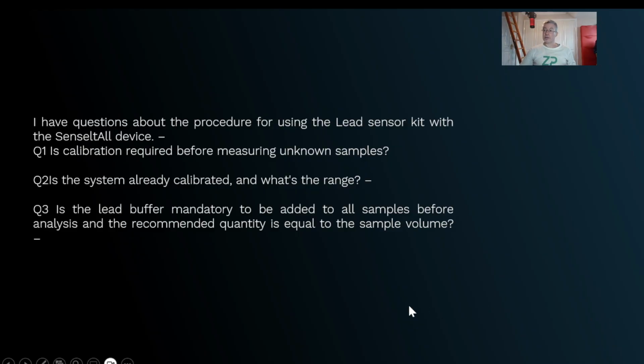Right, so now let me just do a quick recap. Is calibration required before measuring the unknown sample? No, you just saw me. What I've done is I've taken one volume of the unknown plus one volume of the buffer, so that allowed me to control the pH and the ionic strength of that sample. I didn't do a calibration because as long as I'm following my protocols and I'm using these electrodes, then I can use what's called global calibrations.